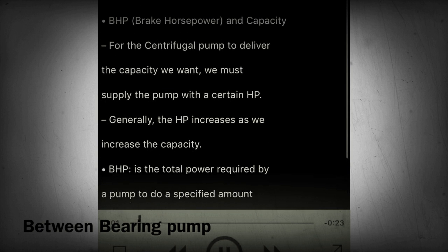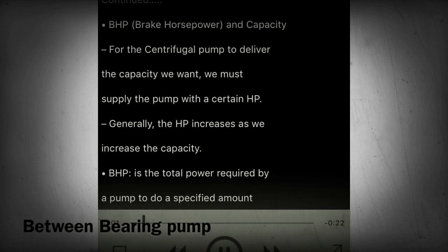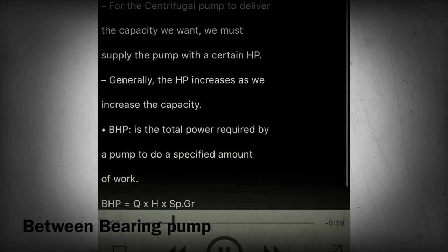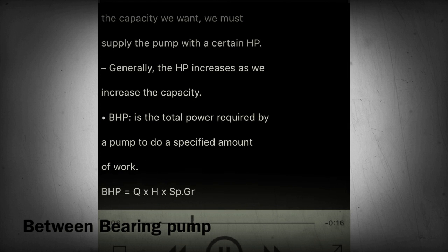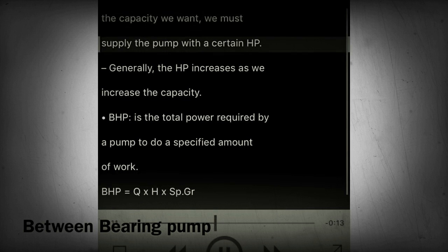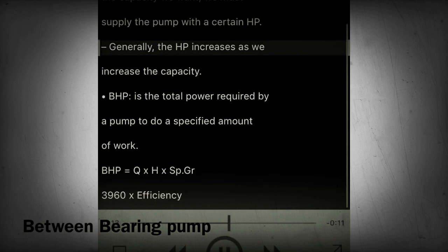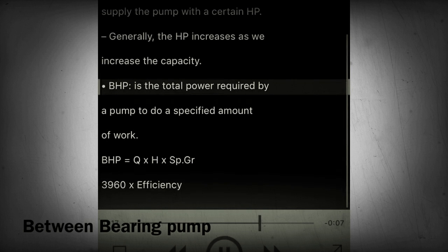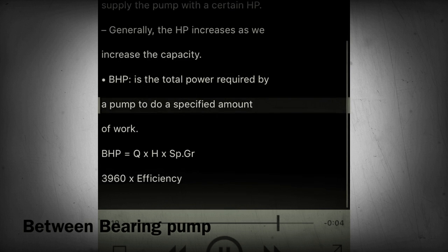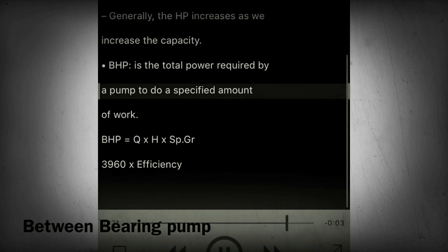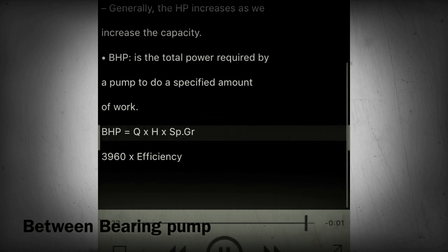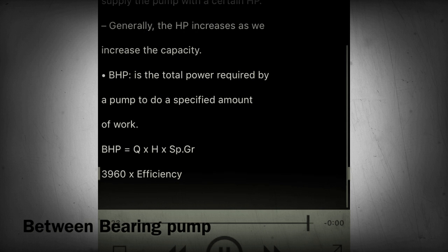Section 23 - Centrifugal pump curves: BHP (brake horsepower) and capacity. For the centrifugal pump to deliver the capacity we want, we must supply the pump with a certain HP. Generally, the HP increases as we increase the capacity. BHP is the total power required by a pump to do a specified amount of work. BHP = (Q × H × SPGR) / (3960 × efficiency).